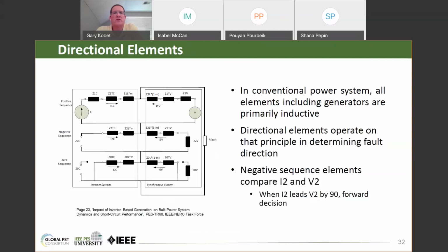And so the reason that in a conventional power system the fault current becomes more lagging is because the elements in the conventional power delivery system are primarily inductive. The transmission lines, the generators, the transformers are all primarily inductive. So when a short circuit occurs and the load is short circuited, then all you have left is essentially inductive elements. And the directional elements in conventional relays have been designed to operate on that principle. The negative sequence elements, in particular, compare the negative sequence current with the negative sequence voltage. And when I2 leads V2, those are the negative sequence quantities, by 90 degrees, a forward decision is made. Next slide, please.